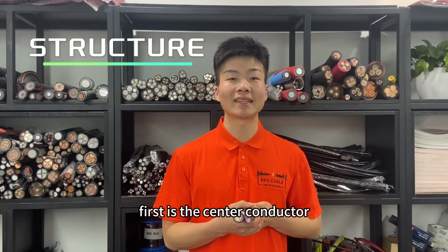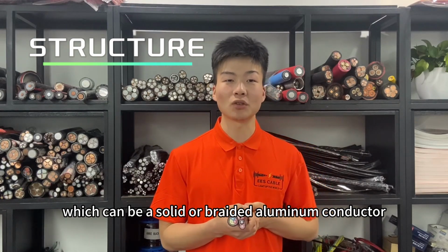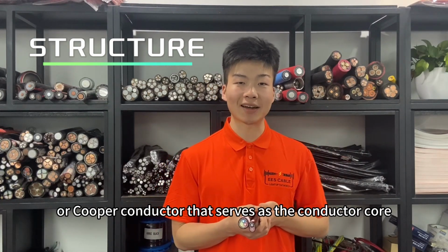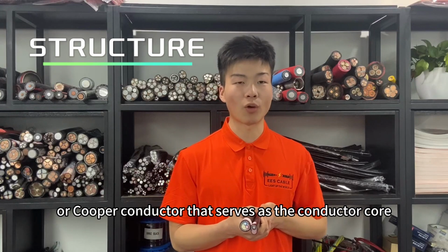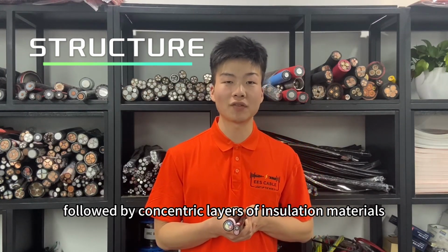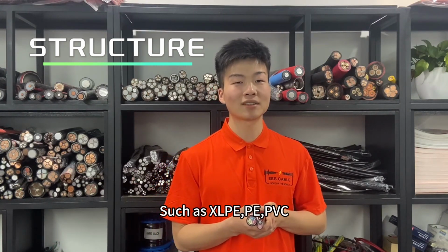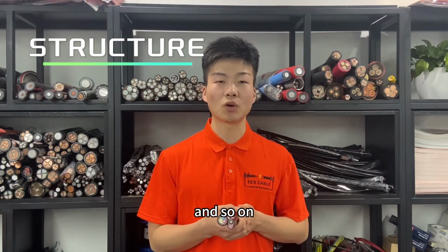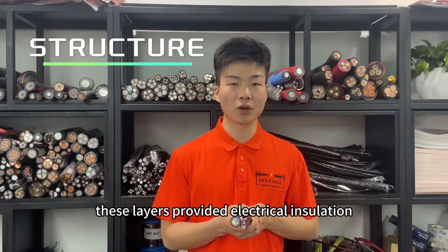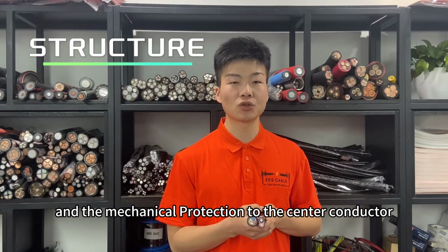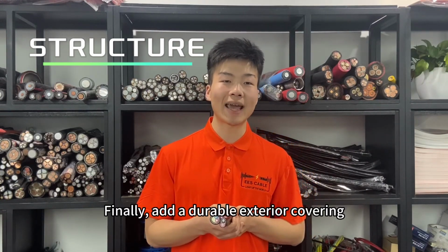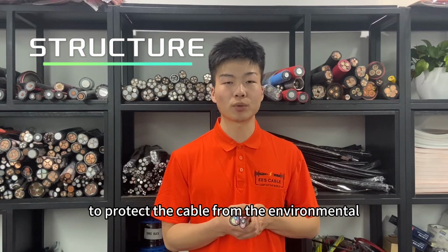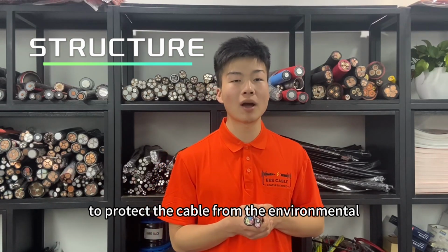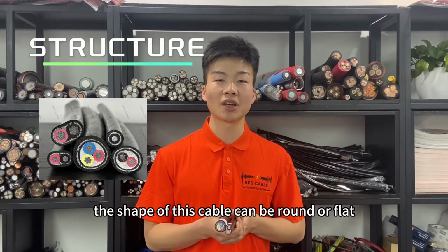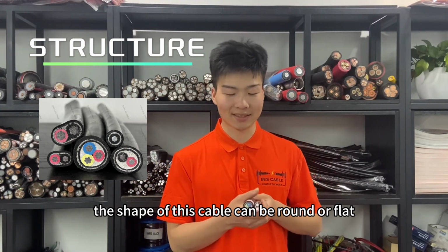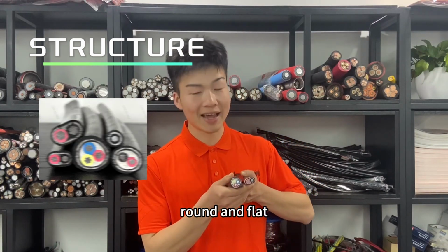First is the center conductor, which can be a solid or braided aluminum conductor or copper conductor that serves as the conductor core, followed by concentric layers of insulation materials, such as XLPE, PVC, and so on. These layers provide electrical insulation and mechanical protection to the center conductor. Finally, add a durable exterior covering to protect the cable from environmental and mechanical damage. The shape of this cable can be round or flat, like this, round and flat.